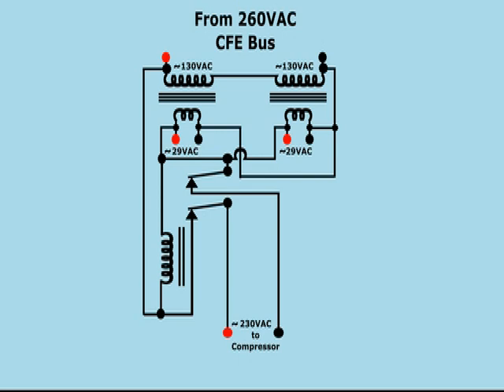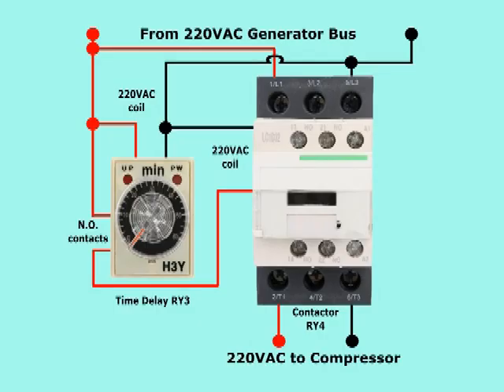For each of the loads, a pair of step-down transformers and a contactor are used, which act independently for each of the loads. As for the generator output bus, it also has a contactor for each compressor, which is activated only when the generator is running. This contactor receives 220 volts of alternating current through a time delay relay, thus delaying the moment its associated compressor can start. An independent time delay relay and contactor are used for each compressor, so that the starting time of the various loads can be separately adjusted.